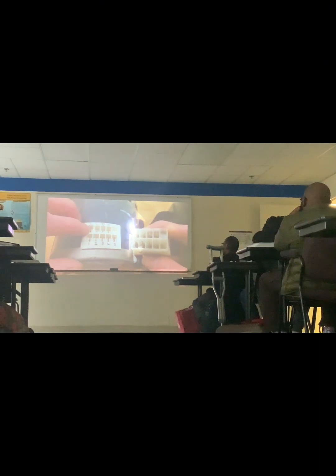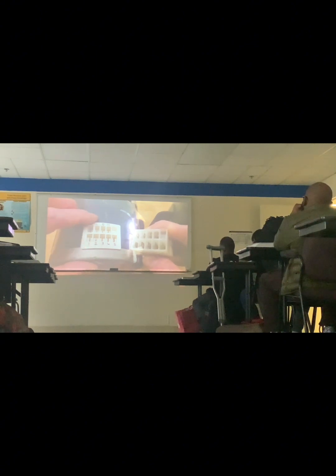Right here is your common for your 24 volts, and you can see that that one's bigger than these. And your speeds are, for your lowest speed is 1, and your highest speed is 5, so you have 24 volt hot signal wires. So this blower motor is only going to turn on when you send 24 volts to the 1, the 2, the 3, the 4, or the 5. So it's only going to be one of these that's going to be hot at a time. And your control board at your furnace or your air handler, that's going to be what's powering the 24 volt signal wire over here to tell this blower motor to turn on. So you're always going to have high voltage to this anytime that the furnace or air handler is on.